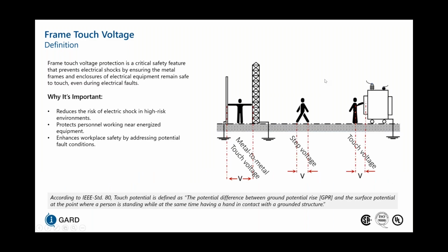So let's begin. For frame touch voltage, the definition is: frame touch voltage protection is a critical safety feature that prevents electrical shocks by ensuring the metal frames and enclosures of electrical equipment remain safe to touch even during electrical faults.